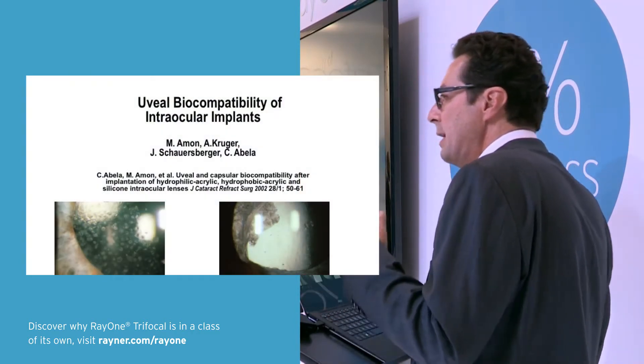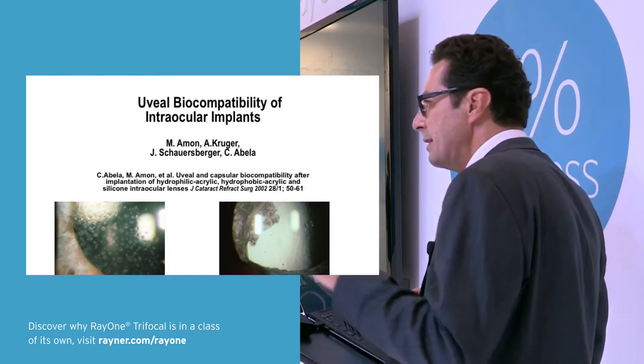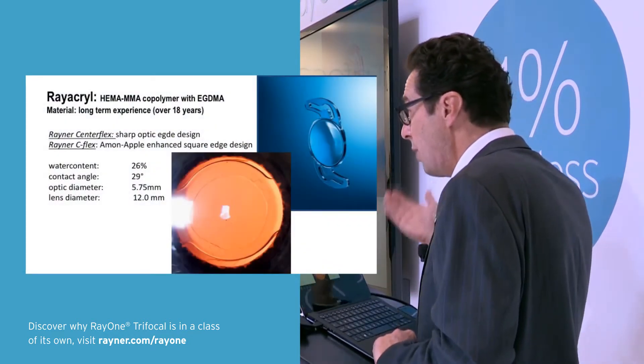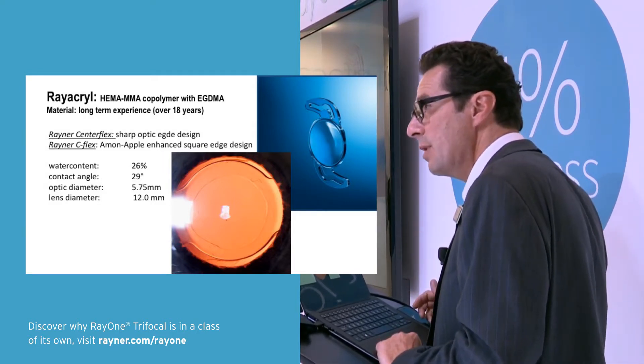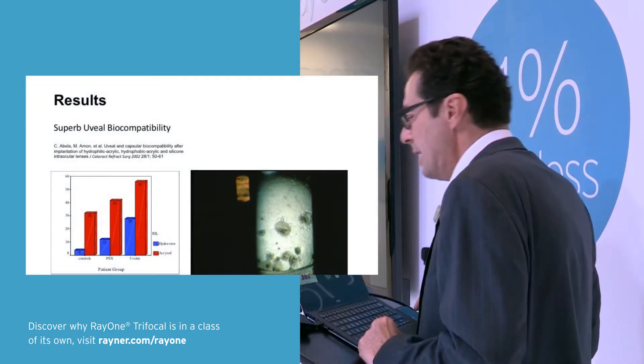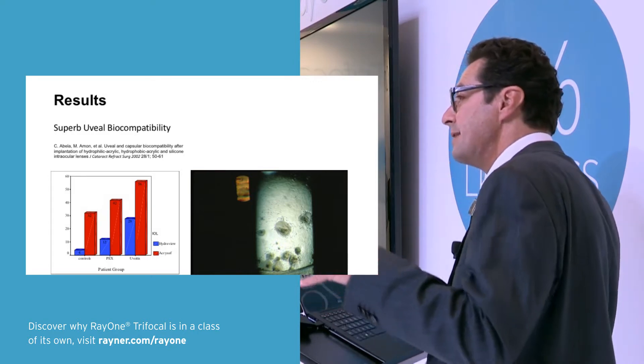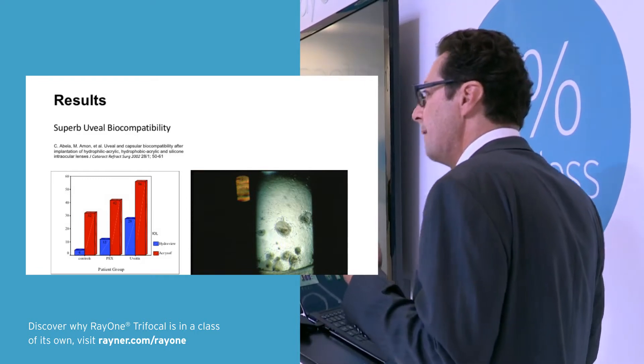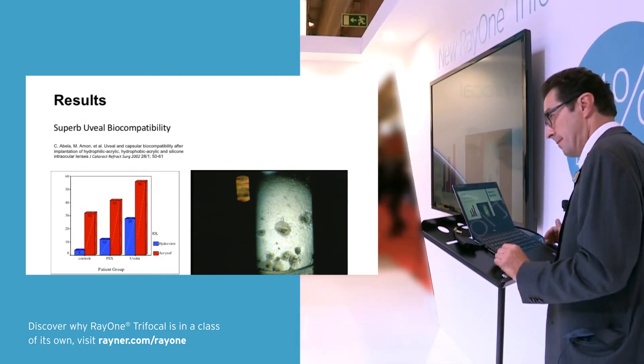It is about 18 years since we first tested this Rayacryl material. We did a lot of studies comparing different IOL materials in different conditions. Rayacryl was the hydrophilic material we tested — it is a 26% water content material. We published these results in 2002, and we found that the uveal biocompatibility was definitely higher and superb compared to silicone or hydrophobic acrylic materials.